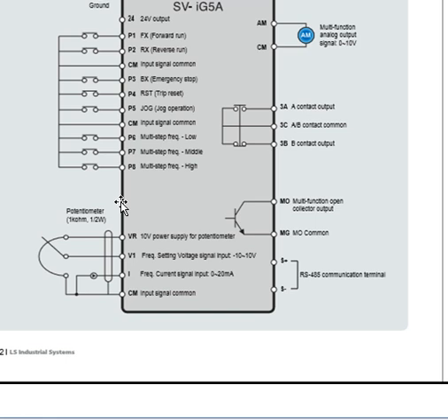And friends, on the left side, down here, there are four terminals. These are used for a variable resistor input. If you would like to use your VFD through a potentiometer, that can be half a watt and 1 kilo ohm, don't exceed the value as recommended by the company. So the VR terminal is going to connect to the potentiometer, and this is the power supply, 10 volt for the potentiometer.